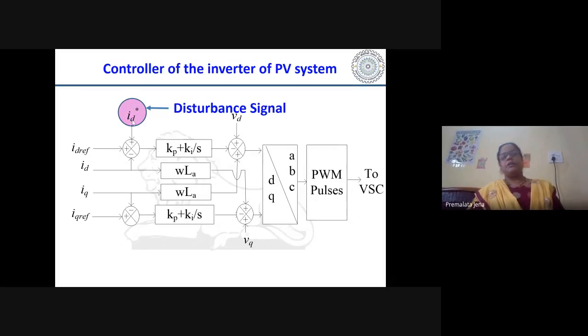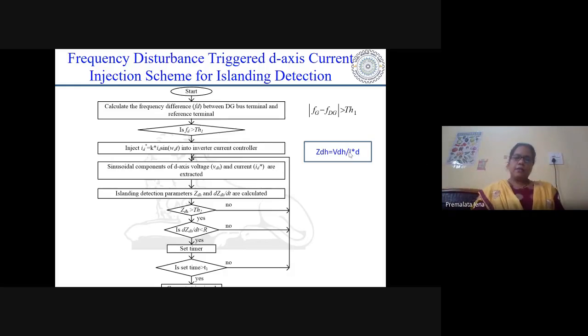Then by injecting the disturbance ID star, you will get some pattern of PWM pulses, which go as a gate signal to the IGBTs of the inverter, and then the corresponding voltage and frequency will be something different. So we take the VD by ID ratio at the terminal of the DG, and decide this Zdh, the D-axis impedance, and if it exceeds a certain threshold, then we say yes, there is islanding, otherwise no.